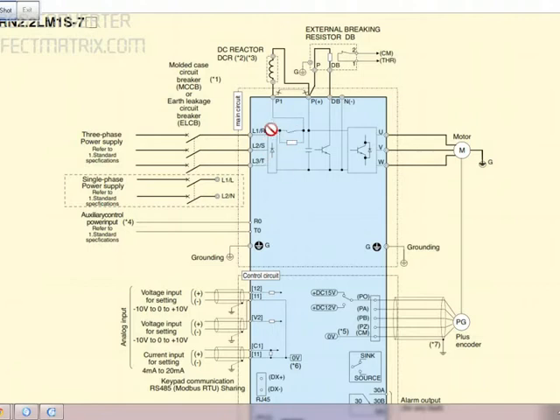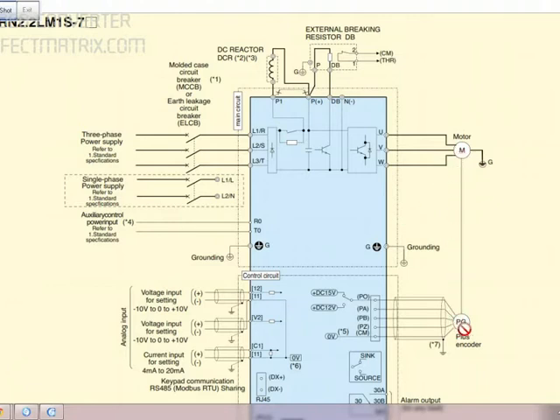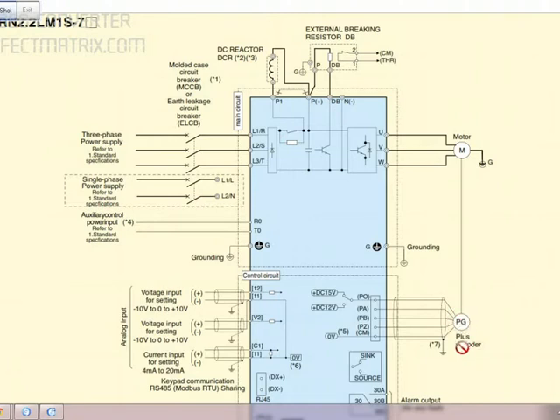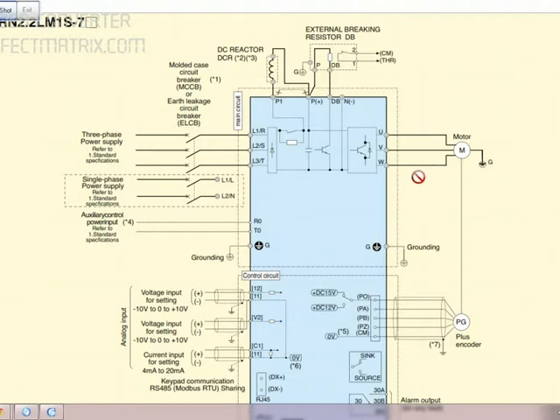It is a three-phase inlet connection here. So you ground the motor here one side. Then from the motor you have the PG connected. PG is for the pulse generator, it is an encoder. So when the motor rotates, it will be able to give the pulse generation and tell which position the motor has moved, to what distance.